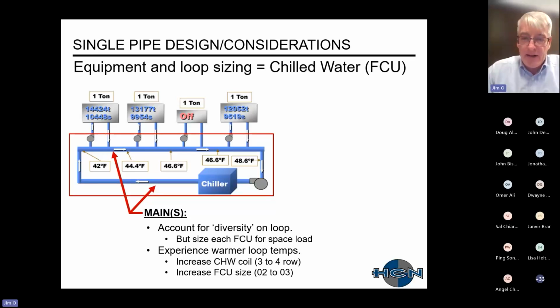So you can downsize that, but you want to make sure that each of the fan coils is sized for the appropriate cooling or heating load that you have for the space. What will happen is, as the water gets warmer and travels down towards the right side of the fan coils here, your water temperature will warm up, as explained. And you can combat that by simply changing, on some of the units, a chilled water coil to go from 3 rows to 4 rows, or to increase from, let's say, a size 2 to a 3. A lot of those changes are really incremental.